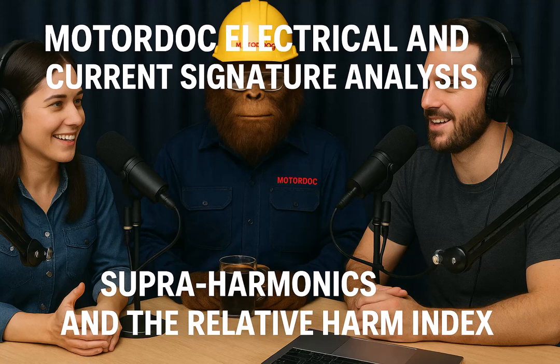Any common examples of equipment that's particularly vulnerable? Definitely. LED lighting is one. Ironically, LEDs can also cause supraharmonics, but they can suffer stress on their driver circuits, shortening their life. Traditional lighting: filament vibration, ballast stress. VFDs themselves can trip unexpectedly or have resonance issues. PLCs, the controllers for automated systems, they can get signal disturbances, operational glitches.